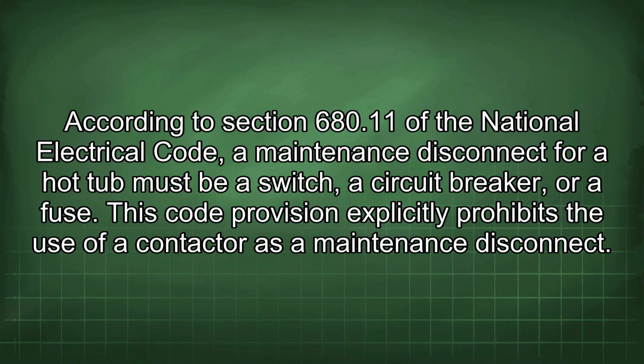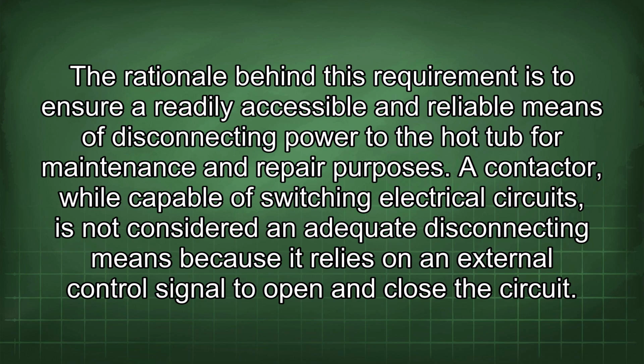According to Section 680.11 of the National Electrical Code, a maintenance disconnect for a hot tub must be a switch, a circuit breaker, or a fuse. This code provision explicitly prohibits the use of a contactor as a maintenance disconnect. The rationale behind this requirement is to ensure a readily accessible and reliable means of disconnecting power to the hot tub for maintenance and repair purposes.